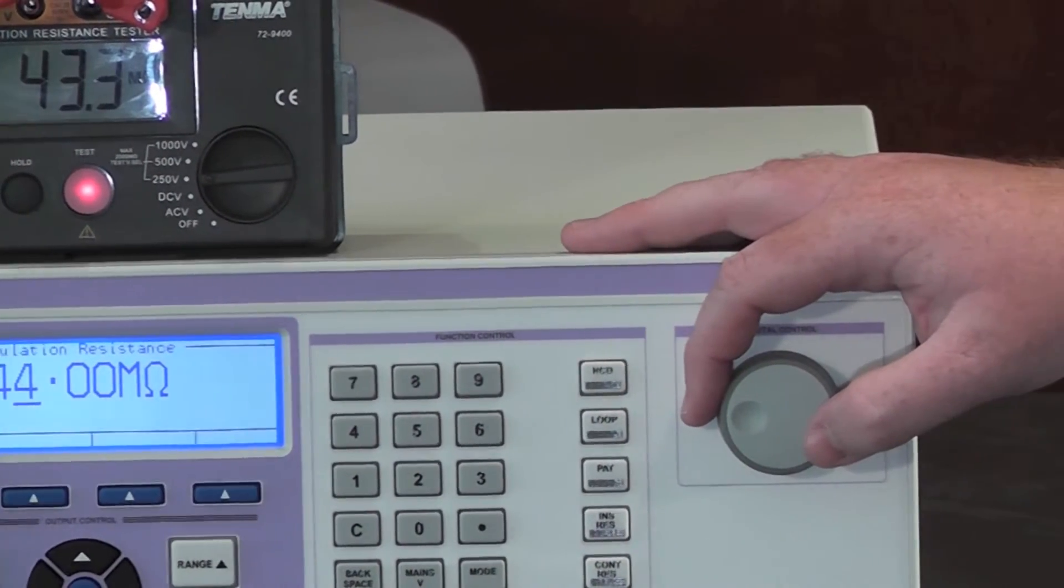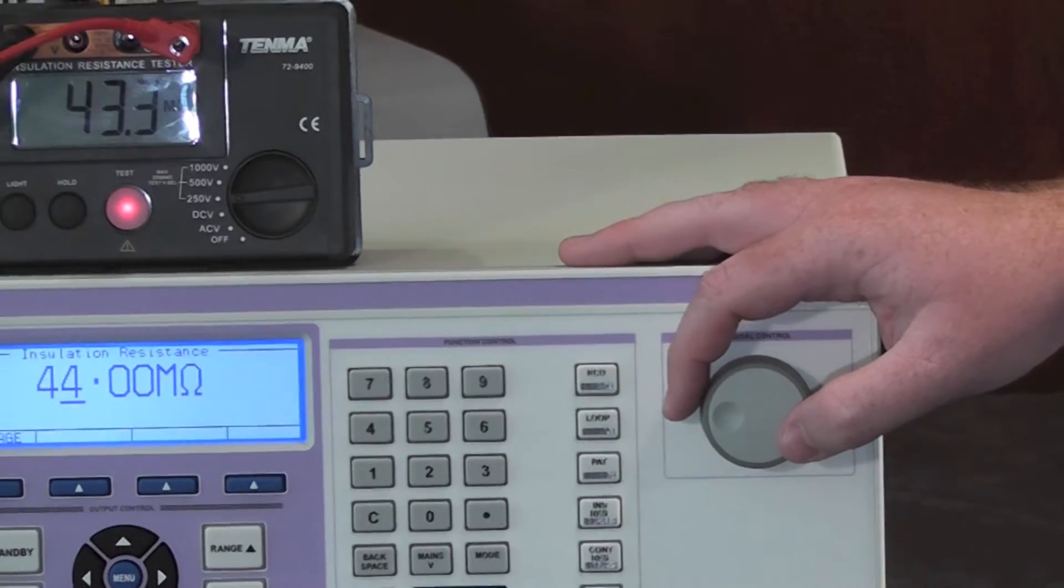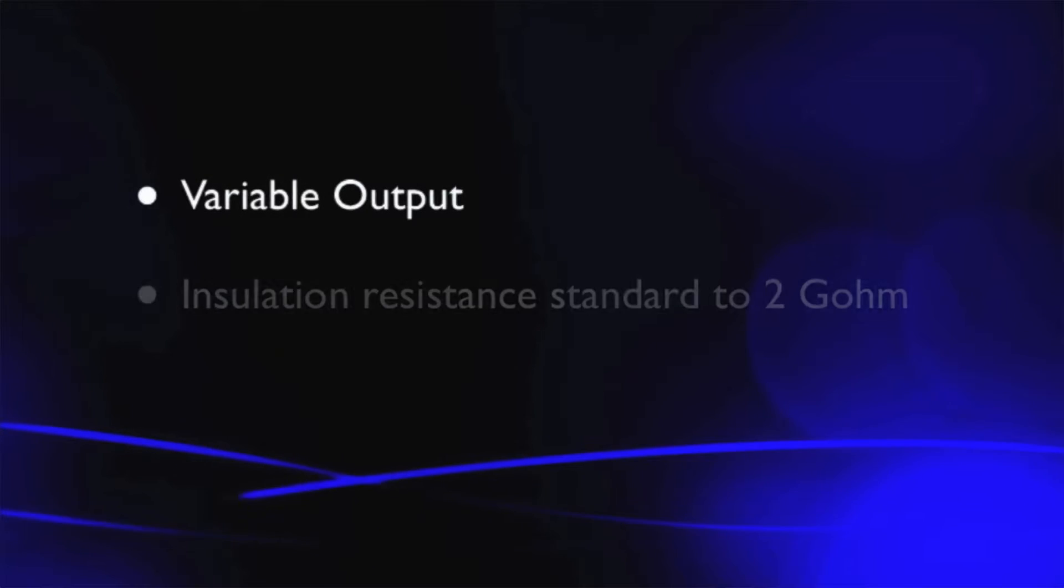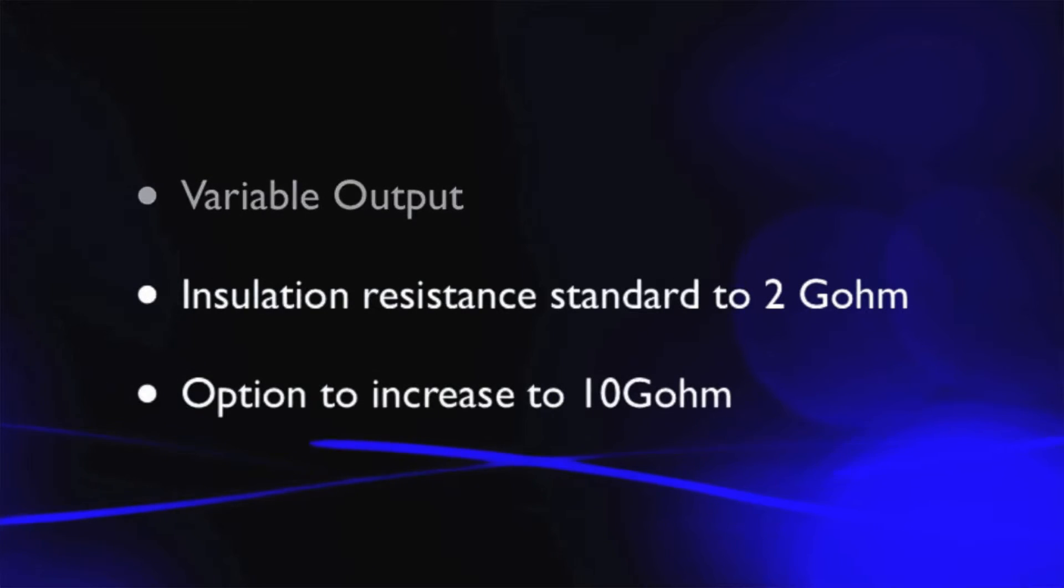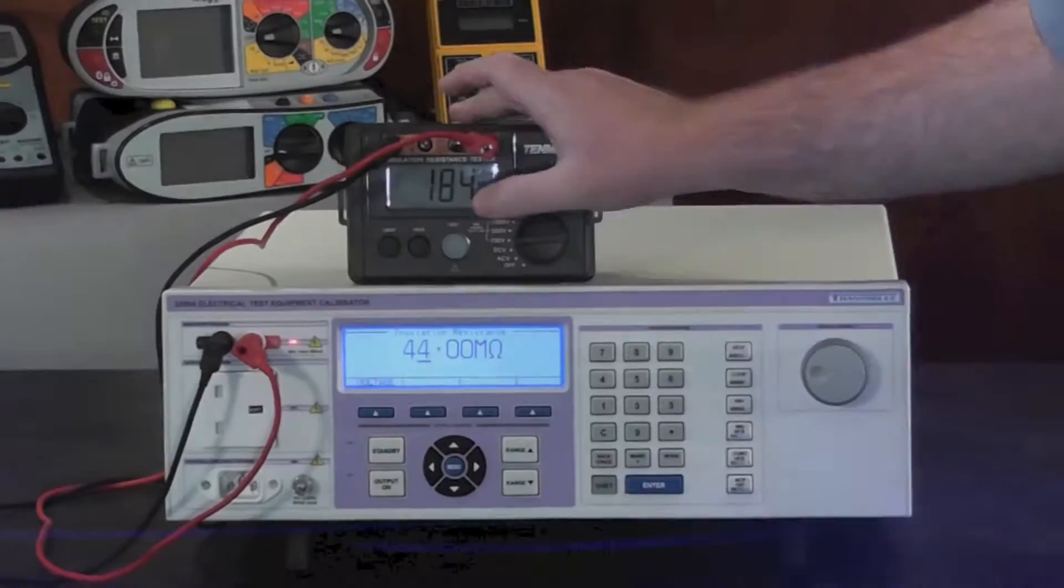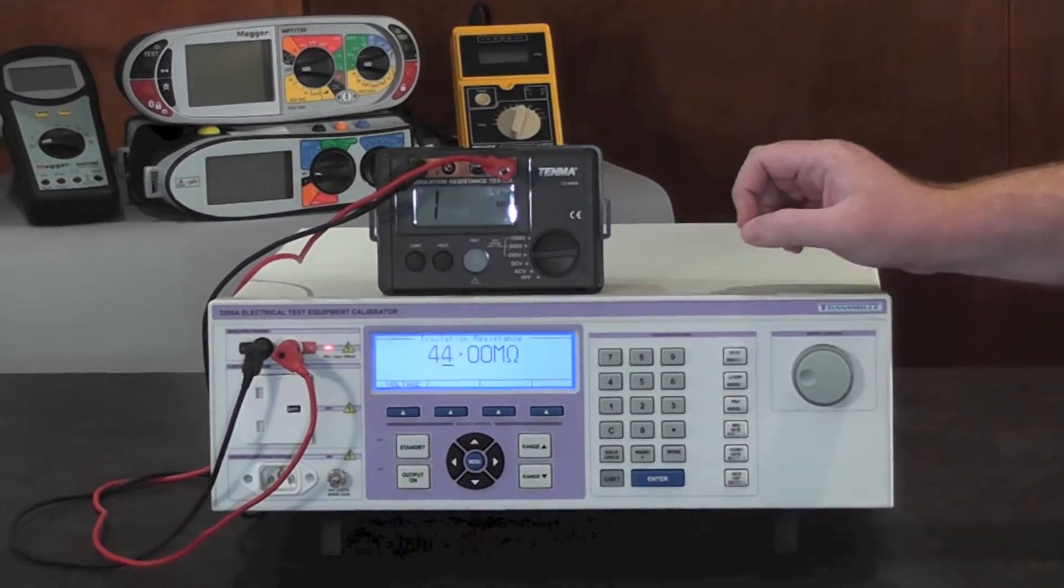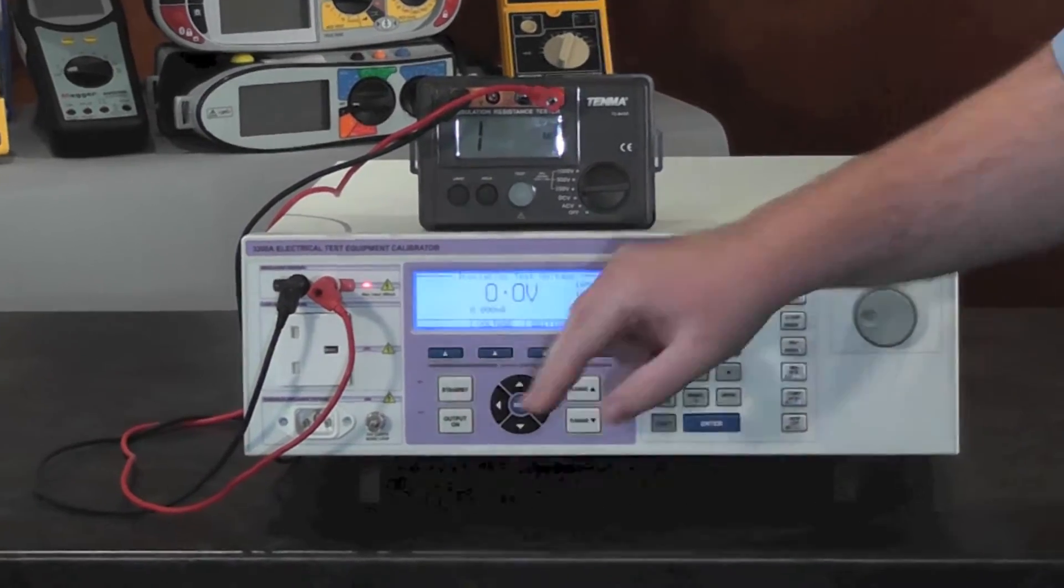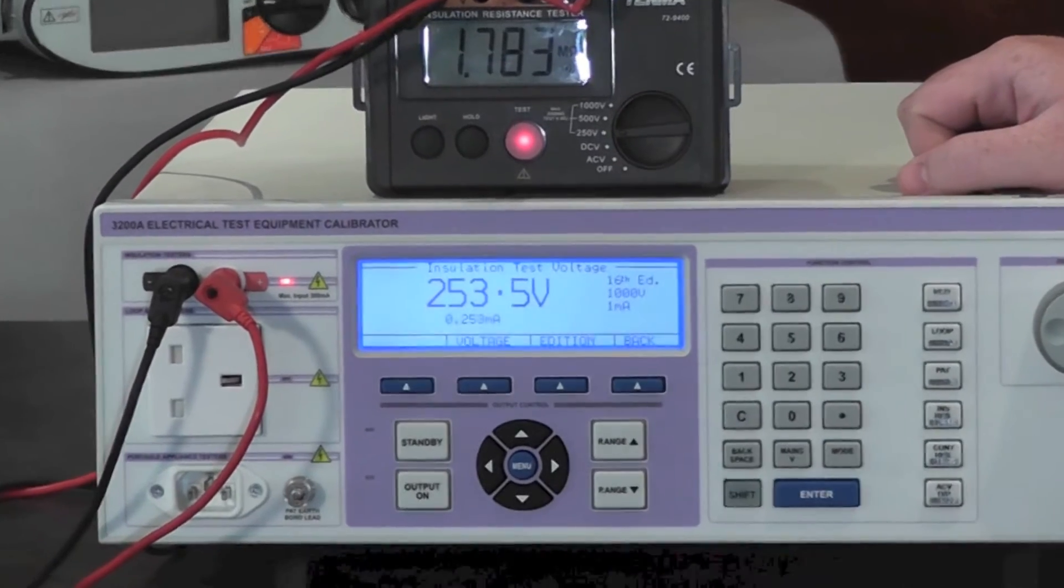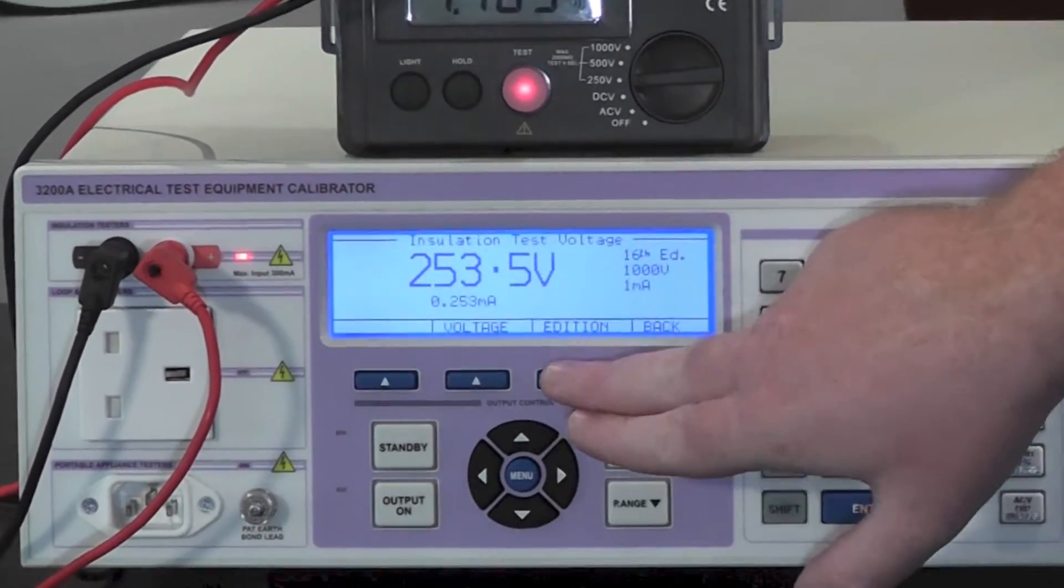The 3200A is fitted with insulation resistance to 2 gigaohms as standard but can be extended to 10 gigaohms. The 3200A also has the ability to measure the test voltage. This can be tested to both 16th edition regulations as well as 17th.